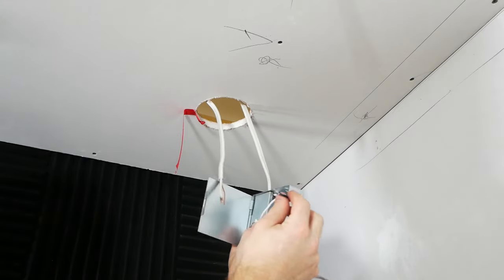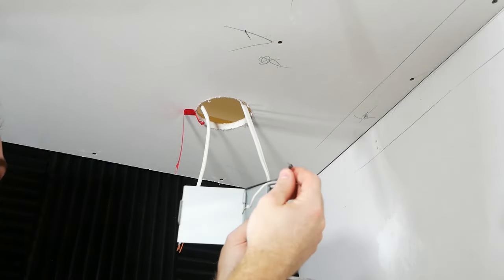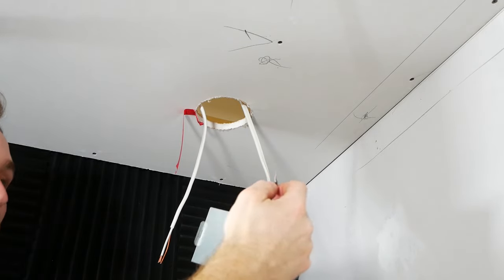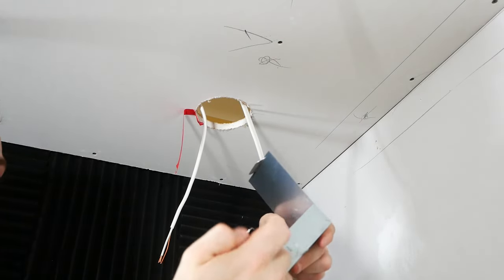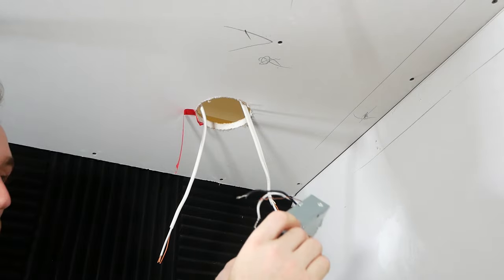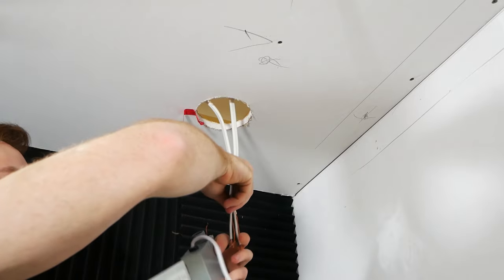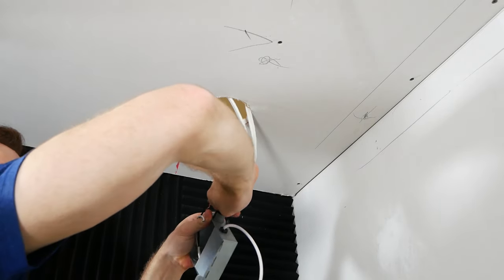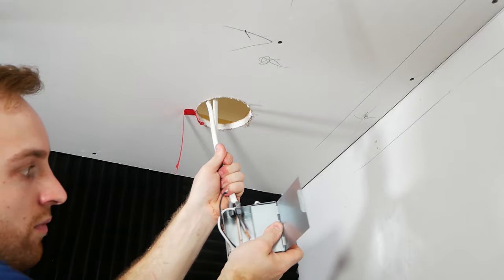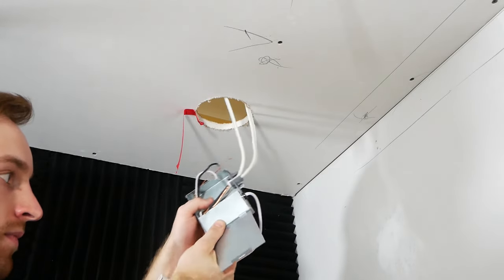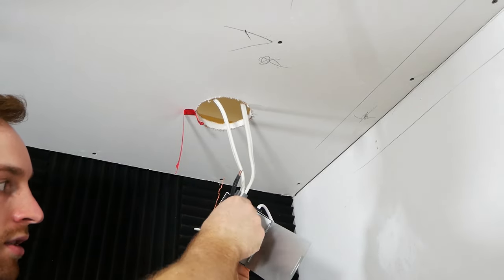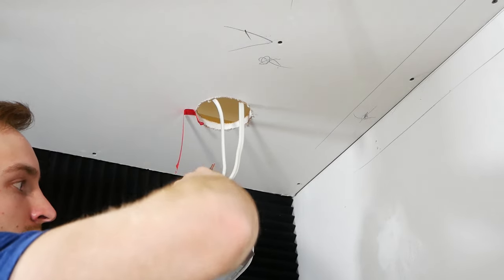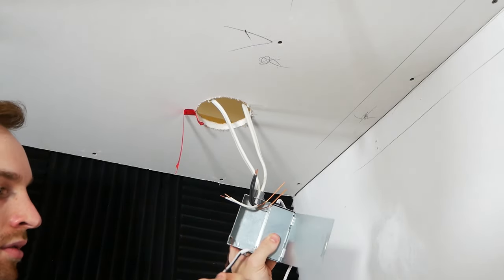So this is a really cheap pot light I have, so the driver is really cheap. If you get a little higher quality one, it will come with quick connects, so that these wires, you don't have to use wire nuts or marrettes or whatever. However, almost all of them, you're going to have a little knockout that you want to knock out. Just comes right out, you can just push it in typically. And then take a plastic connector, just a half inch, and put it in. I'm going to line my wires up to be side by side. Keep everything nice and straight, and I'm going to push it in to the connector. And I just want to push enough in, so that I have the jacket of my Romex just through the connector. Okay. I'm going to start separating everything. The blacks go together, the grounds can go together, and then the whites we can put together on the side there, keeping everything separate.